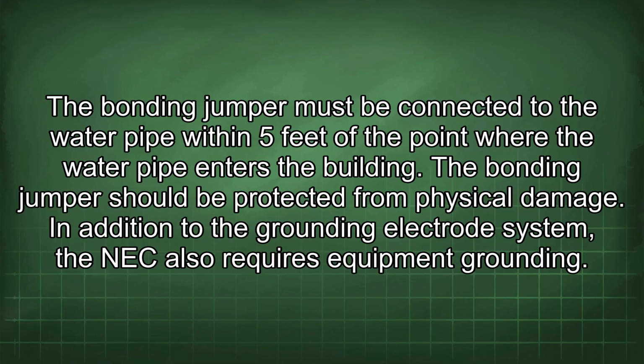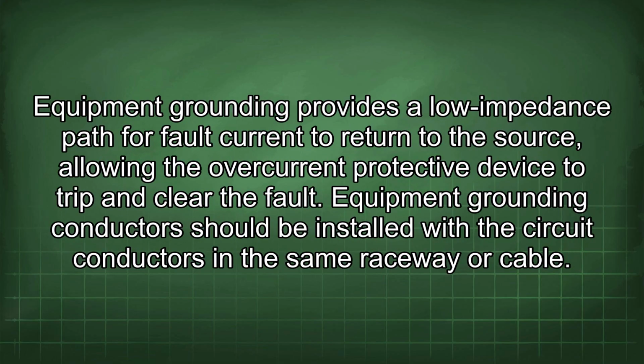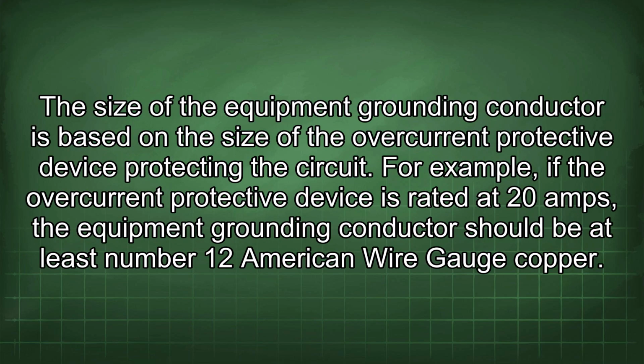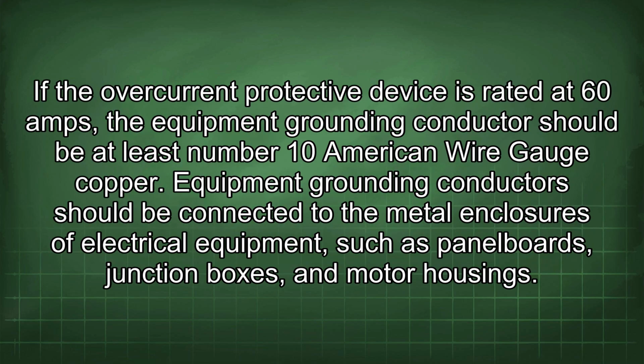In addition to the grounding electrode system, the NEC also requires equipment grounding. Equipment grounding provides a low impedance path for fault current to return to the source, allowing the overcurrent protective device to trip and clear the fault. Equipment grounding conductors should be installed with the circuit conductors in the same raceway or cable. The size of the equipment grounding conductor is based on the size of the overcurrent protective device protecting the circuit. For example, if the overcurrent protective device is rated at 20 amps, the equipment grounding conductor should be at least number 12 American wire gauge copper. If the overcurrent protective device is rated at 60 amps, the equipment grounding conductor should be at least number 10 American wire gauge copper.